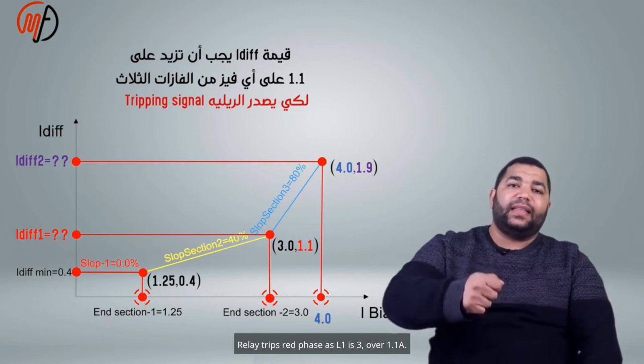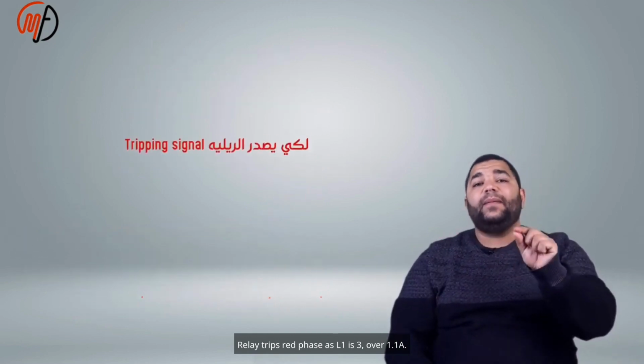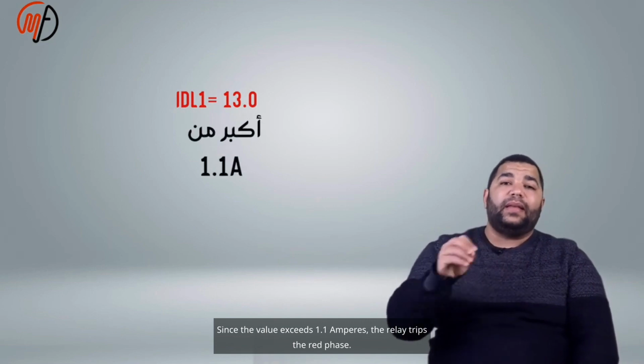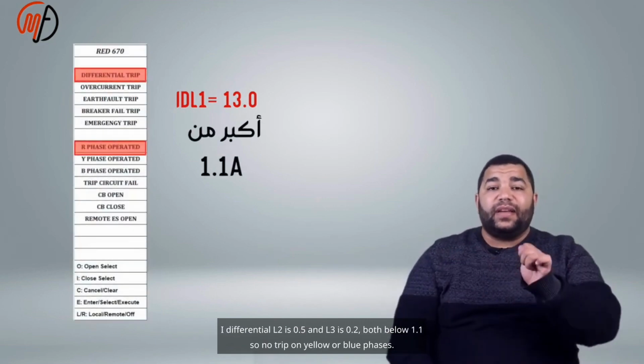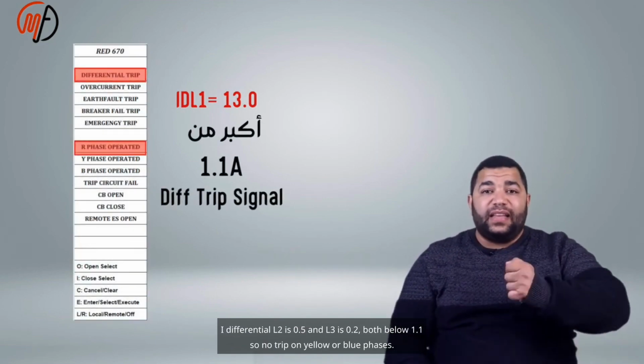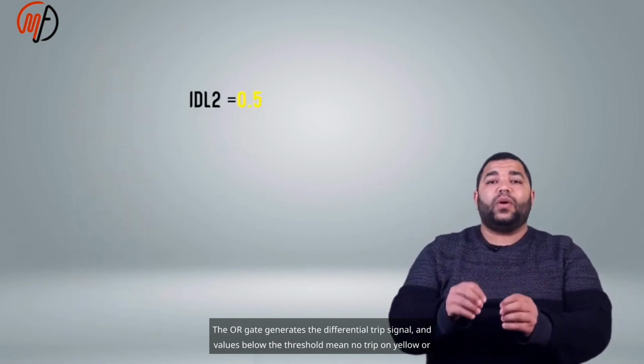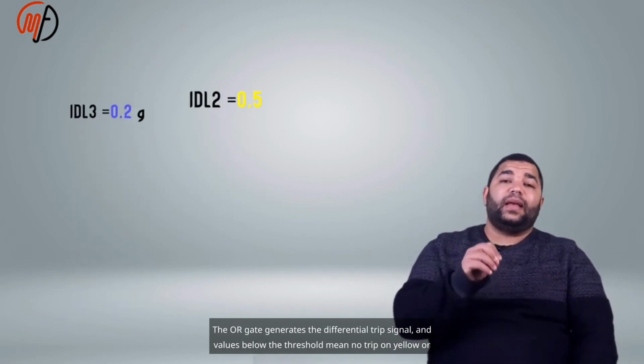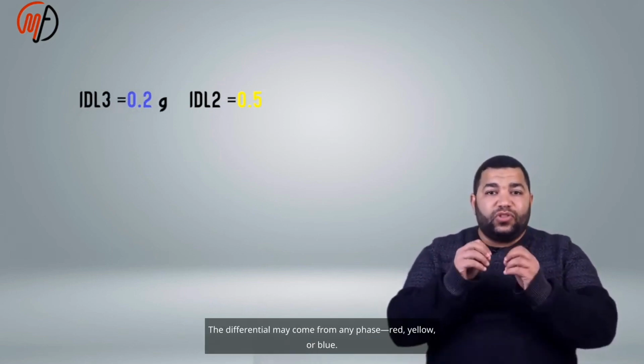The relay trips the red phase as I differential L1 is 3, over 1.1 A. Since the value exceeds 1.1 amperes, the relay trips the red phase. I differential L2 is 0.5 and L3 is 0.2, both below 1.1, so no trip on yellow or blue phases. The OR gate generates the differential trip signal, and values below the threshold mean no trip on yellow or blue.